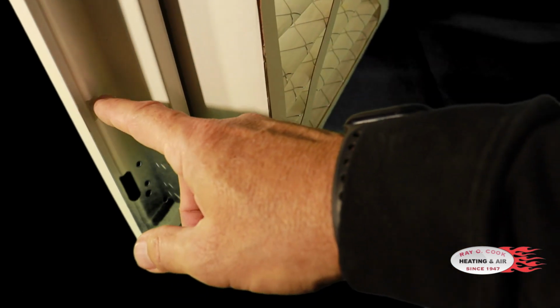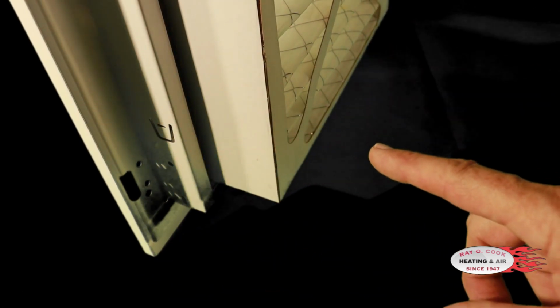So that when you open your filter grill, from the ceiling up needs to be at least 12 inches thick here, so that we can suck all of the air through this filter. If you have a box sitting right down on top of this, then the round duct is only going to filter the air. These corners will not filter the air, and we'll look at that on an actual house. There may be some modification needed to your sheet metal box to accommodate better air quality here.